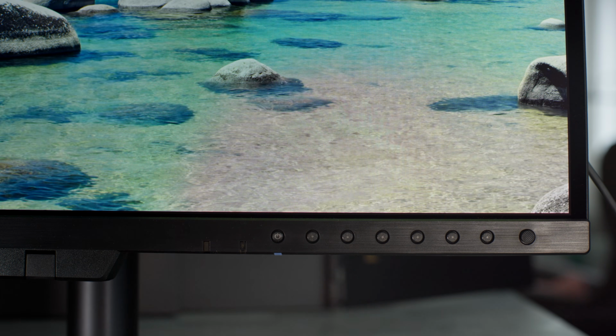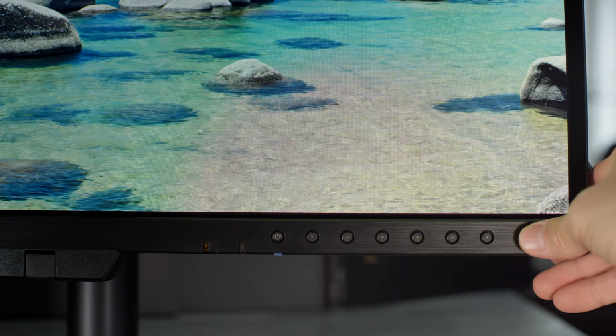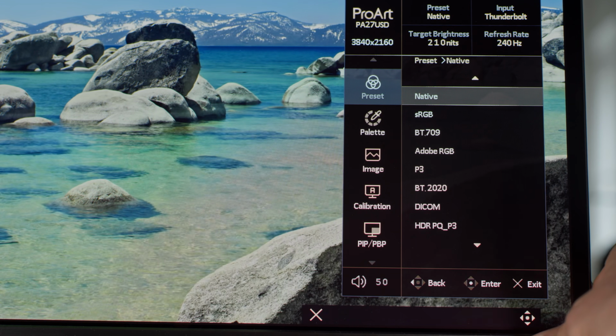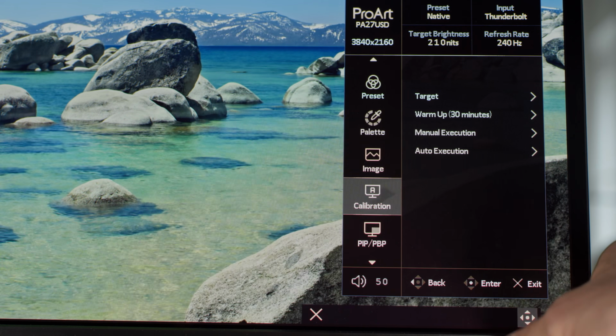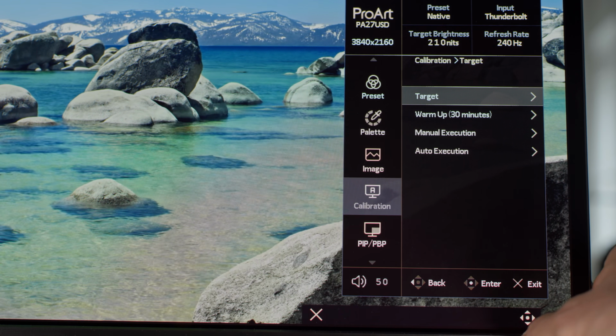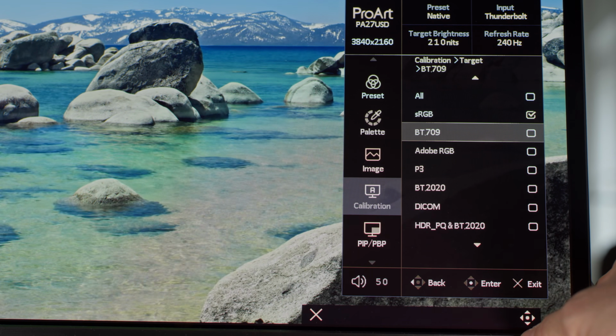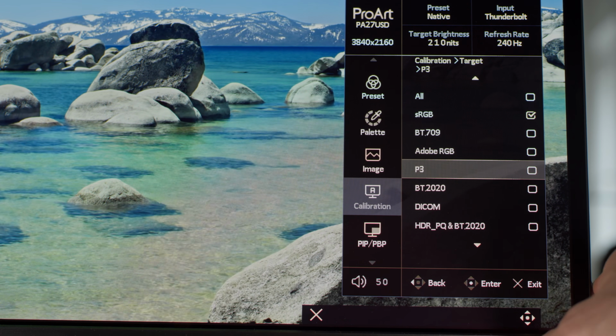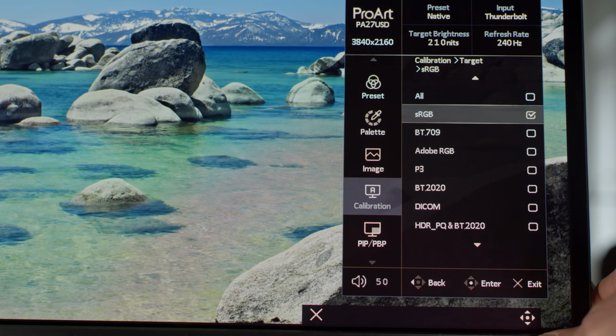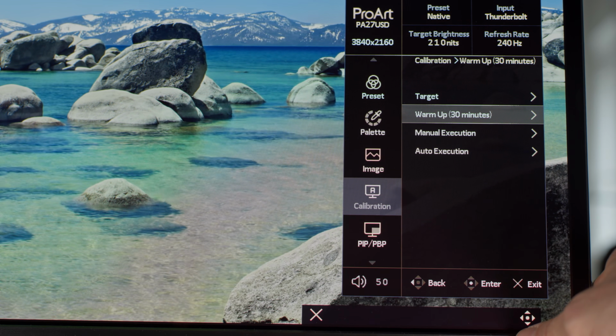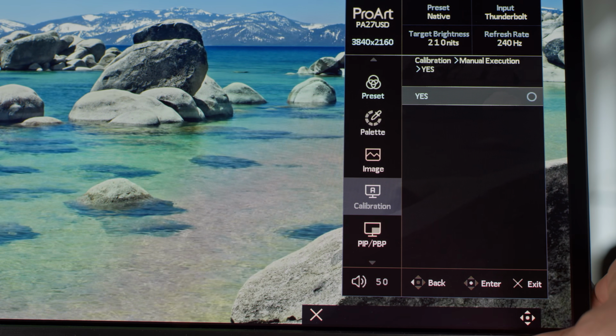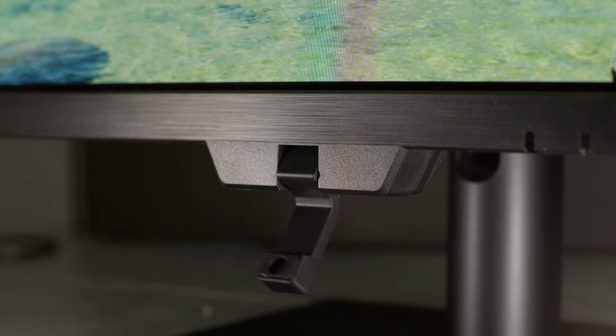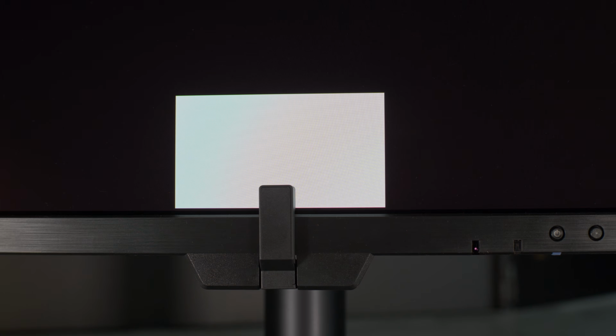Okay, now let's start with the manual calibration that is possible on this monitor. Here you can see the presets. I've set mine to native now, and in the calibration, of course, you can set the target color space. So it would be sRGB or Rec.709 or DCI P3, but in my case it's sRGB. And then you can let it warm up for 30 minutes, and then you can manually execute the calibration. And pretty cool, you can see that the small internal colorimeter is moving out of the monitor, and in a few seconds the internal calibration will start.